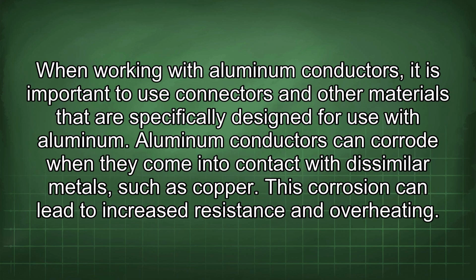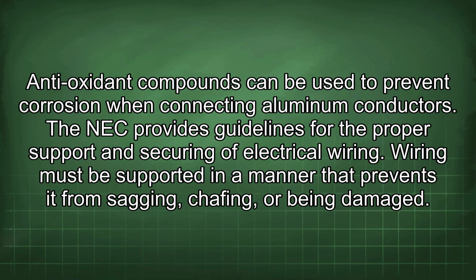When working with aluminum conductors, it is important to use connectors and other materials that are specifically designed for use with aluminum. Aluminum conductors can corrode when they come into contact with dissimilar metals, such as copper. This corrosion can lead to increased resistance and overheating. Antioxidant compounds can be used to prevent corrosion when connecting aluminum conductors.